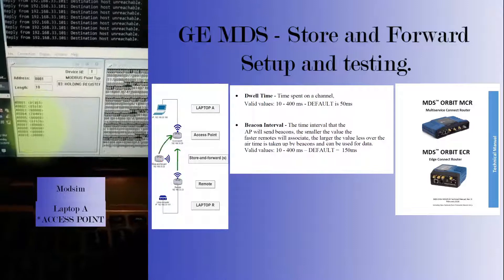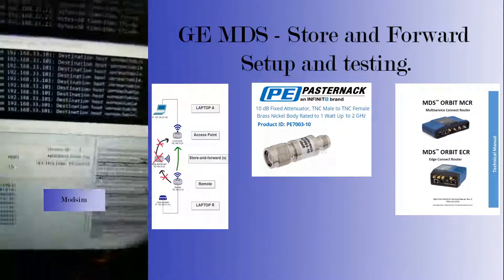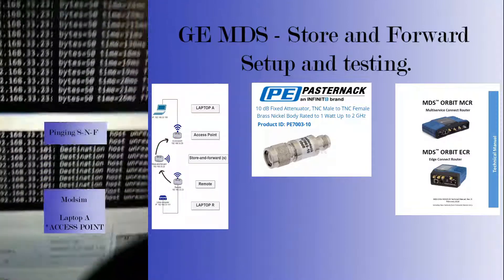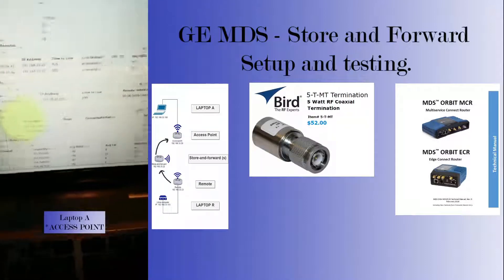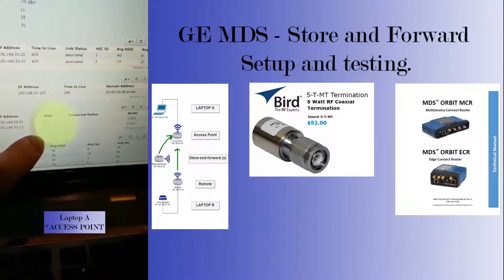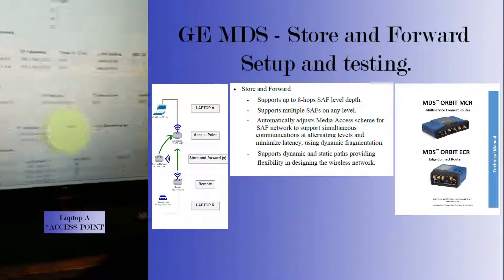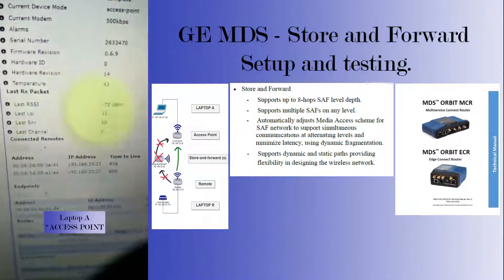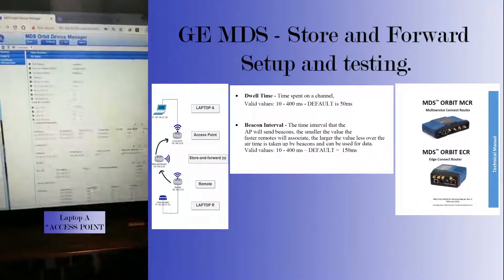We still have traffic. Modbus is still polling. We can see that our ping to our store-and-forward is no longer working, but our ping to our remote still is. If we look at the GUI, we can see our routes, and we have only one hop — indicating that these units are talking directly to the AP, not going through anything. We can see our RSSI to the last RSSI to the unit. It works.